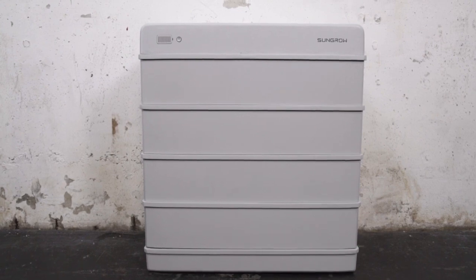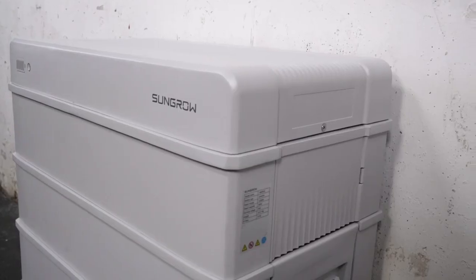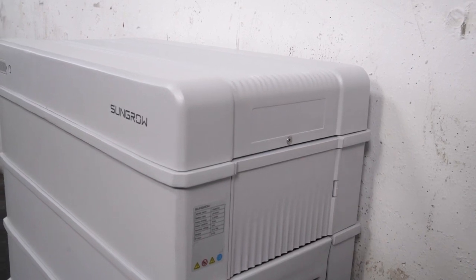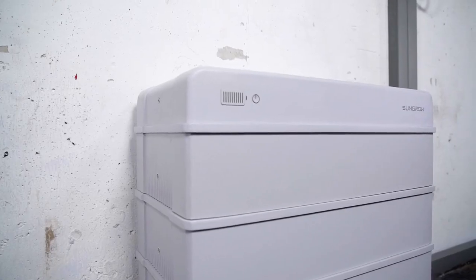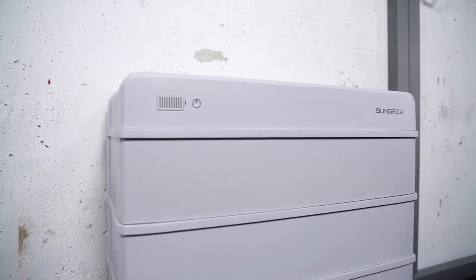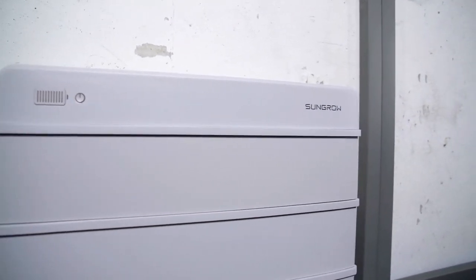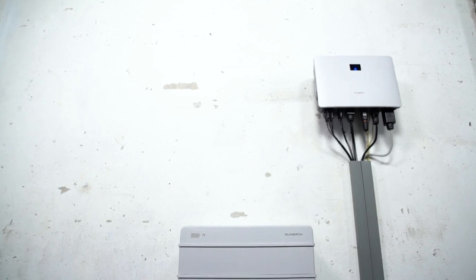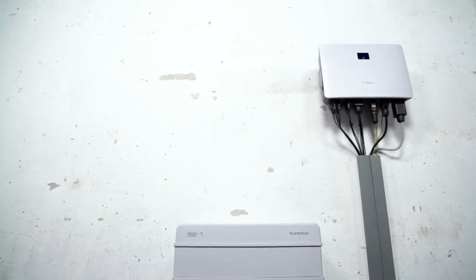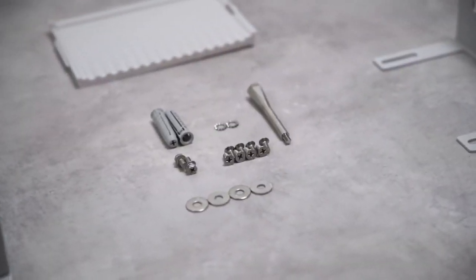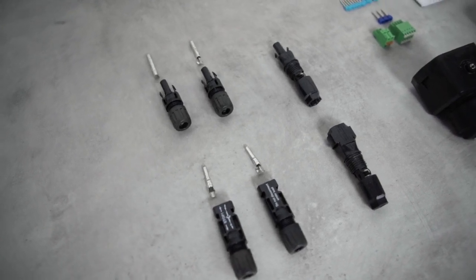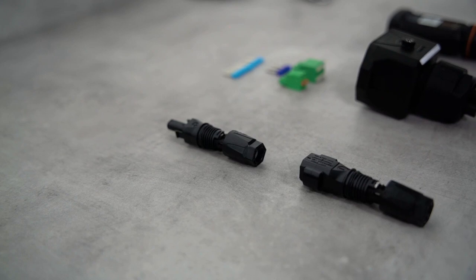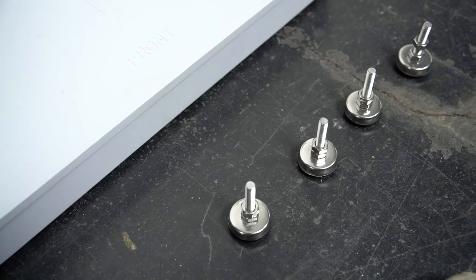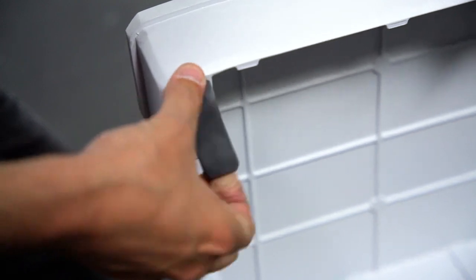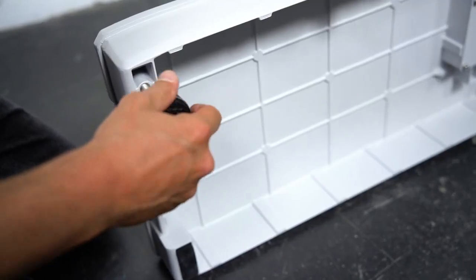You need a suitable place for the single-phase solution. This means it should be a room where no flammable materials or gases are stored. The ambient temperature should always remain between 0 and 45 degrees Celsius. Furthermore, the battery needs to be well ventilated and should not be exposed to direct sunlight, rain or snow. All screws and connectors required for the installation are already included in the delivery. You only need cables and your own tools like screwdrivers. In case it's needed, you can add height-adjustable feet to the battery. They are part of the delivery scope.